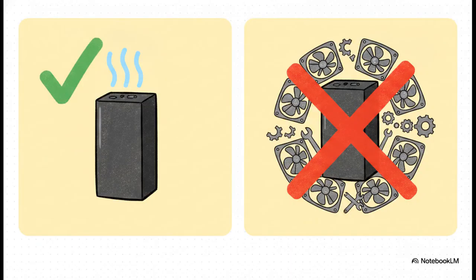Let's break down exactly why that natural cooling is such a game-changer. Competitor units operating at these high capacities almost always rely on forced air cooling. And that means dedicated fan power, rotating mechanical components, and heavy maintenance in spaces where you can barely even fit a wrench. But the RESIBLOC cools itself naturally. Dropping the fans means one less rotating, maintenance-hungry component in your transformer room. Simply put, less to fail and less to maintain in a space that's already incredibly tight.